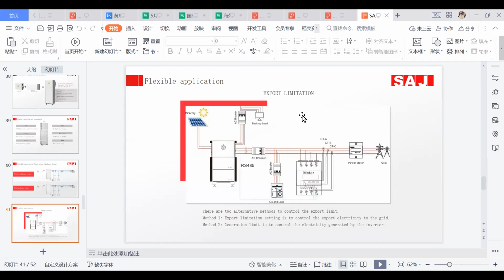And we also have the export limitation. That means no interaction with the grid. We have 2 modes. One is the total power mode. That means the sum of the 3 phases, both export and import, is 0. The other is the each phase power mode. That means every phase is controlled to have 0 watt to the grid, because different countries have different regulations or safety requirements. For example, in Germany they use the total power mode, and other countries like the Czech Republic use the each phase power mode.